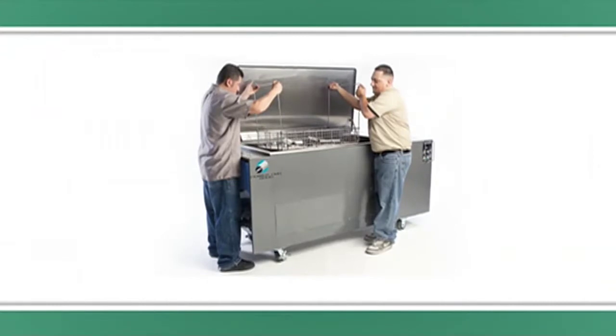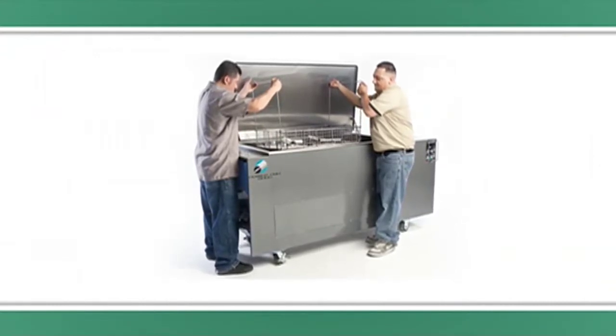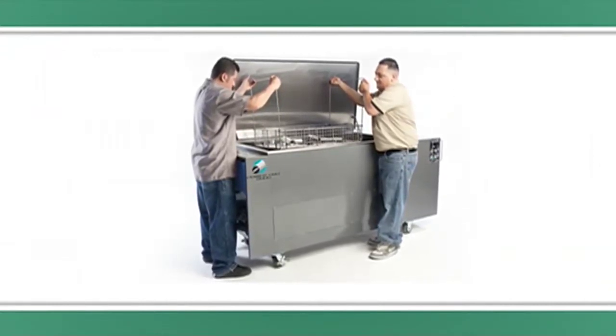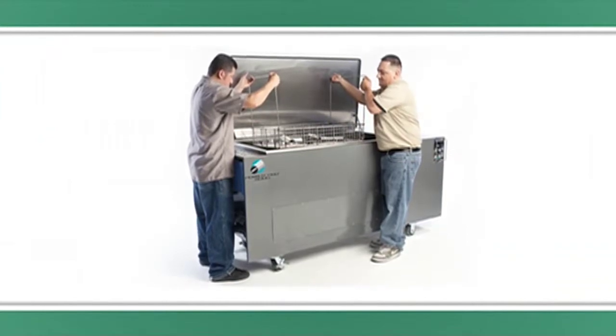Ultrasonic components used by OEMs consist of direct bonded tanks, transducers, and ultrasonic generators. For larger tanks, those above 50 gallons, immersible transducers are either bolted or hung on the bottom and/or sides of the tank. The generators can be located remotely from the tank.